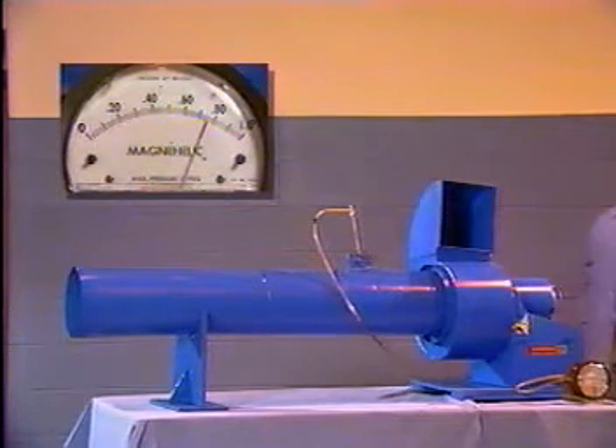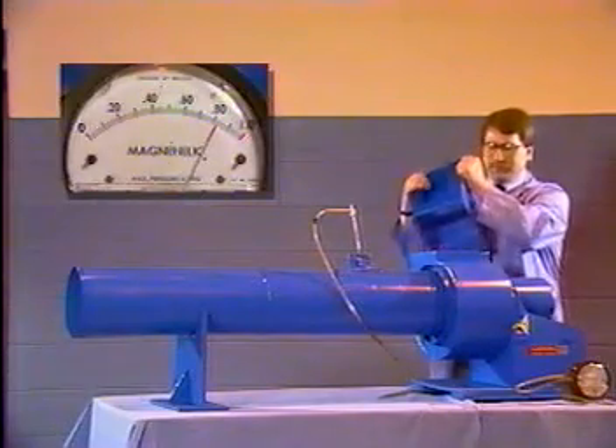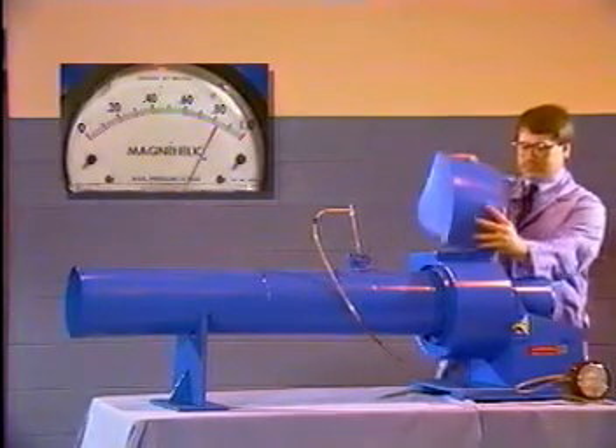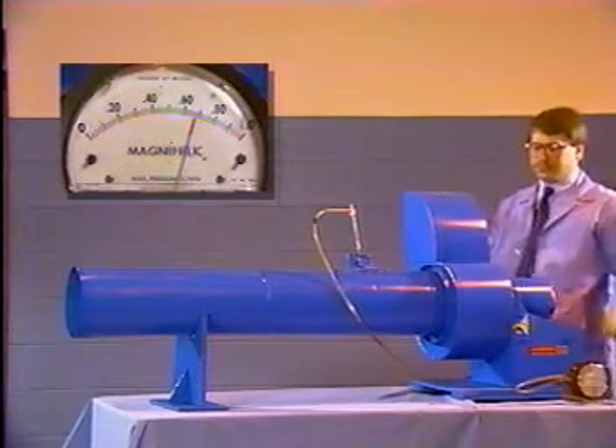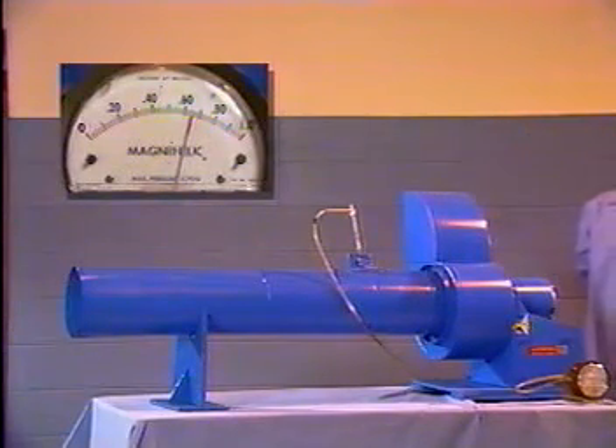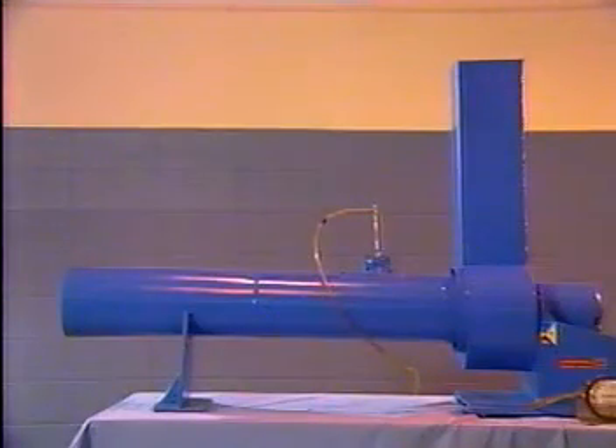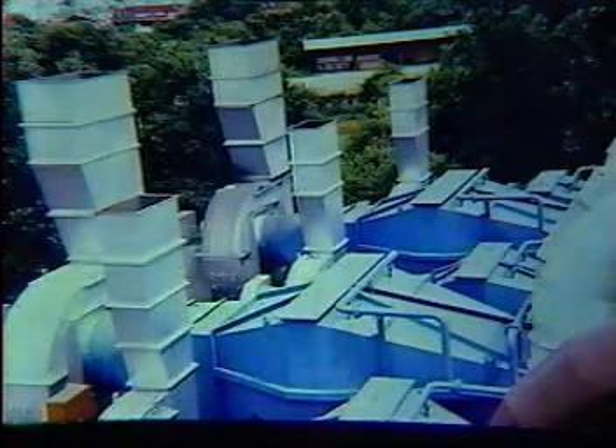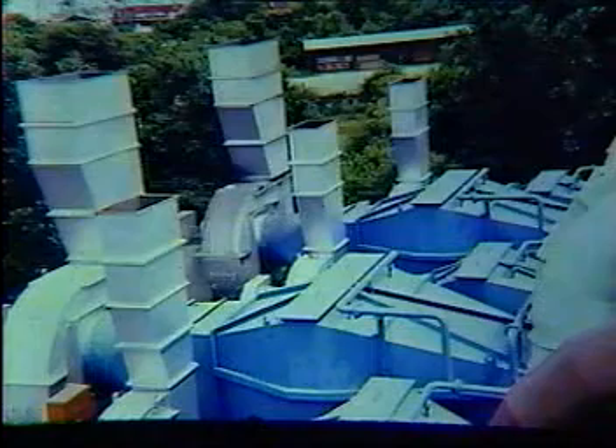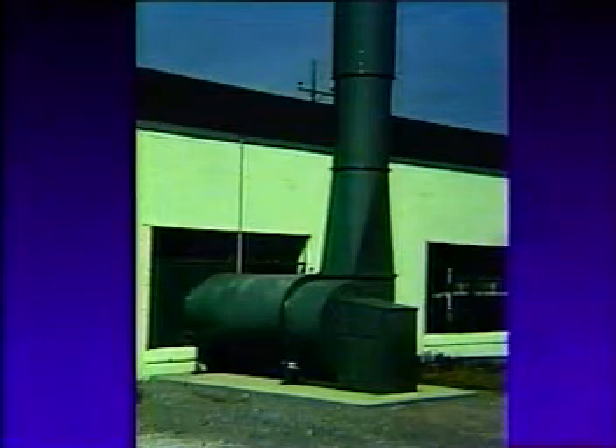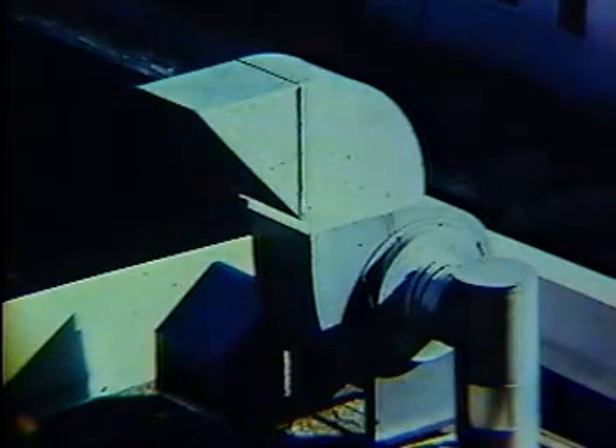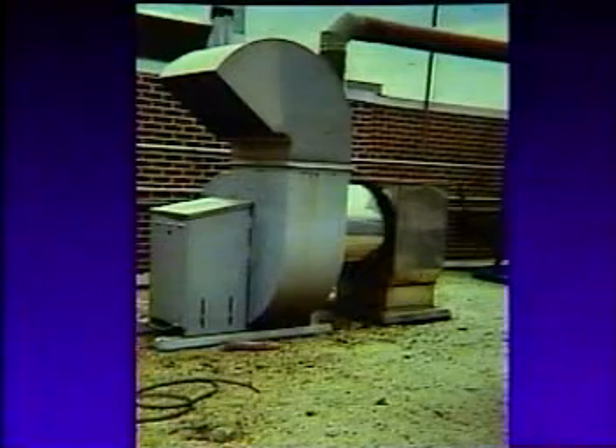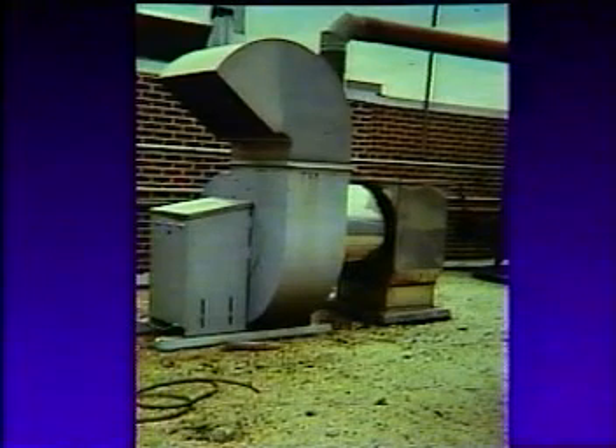In this way, your loss will not be as great as it would be if the elbow turns against the direction of flow. As you can see, efficiency can be lost when the elbow is turned against the direction of flow. For maximum outlet efficiency, of course, air should be discharged through a straight outlet duct. Straight is the word to keep in mind when designing inlet or outlet ductwork, because fans are able to develop more pressure when they are fitted with straight ducts. Any abrupt turns at the inlet or outlet will result in system effects that significantly disrupt airflow.